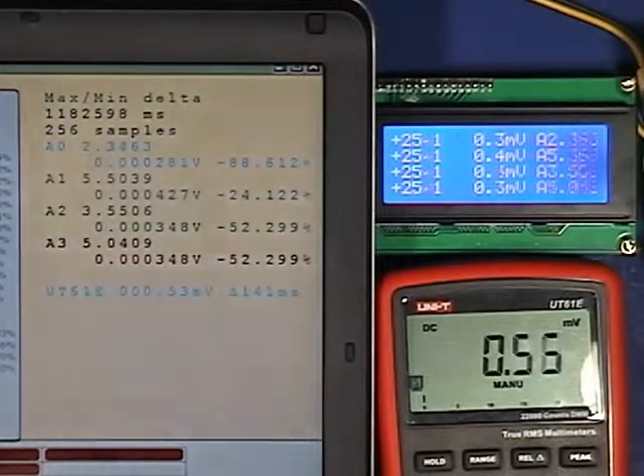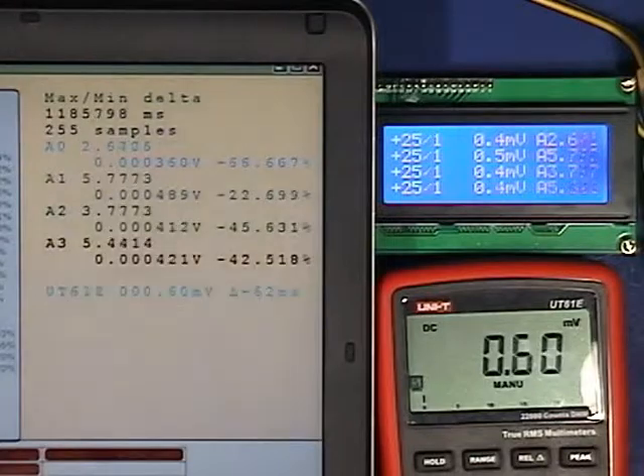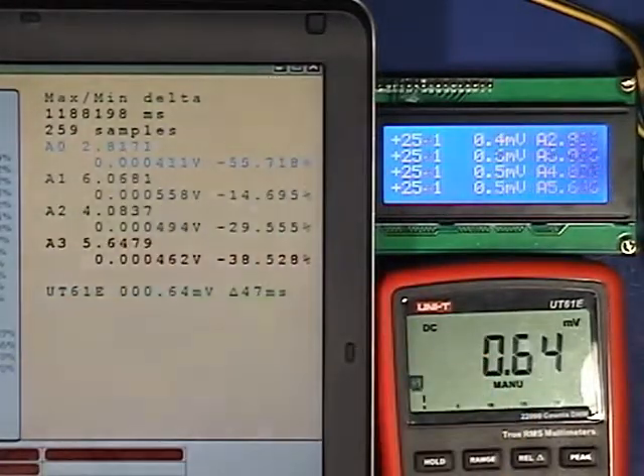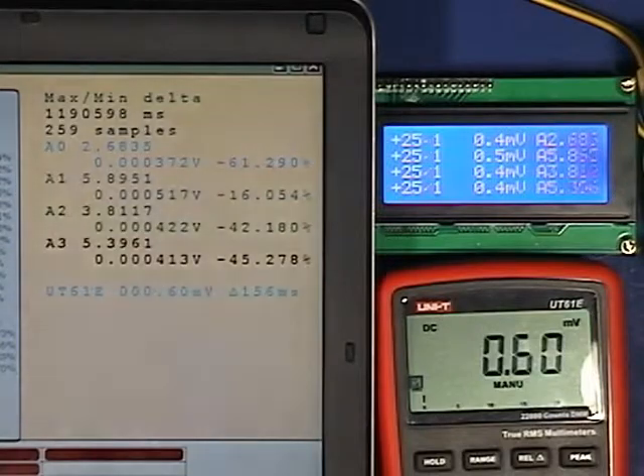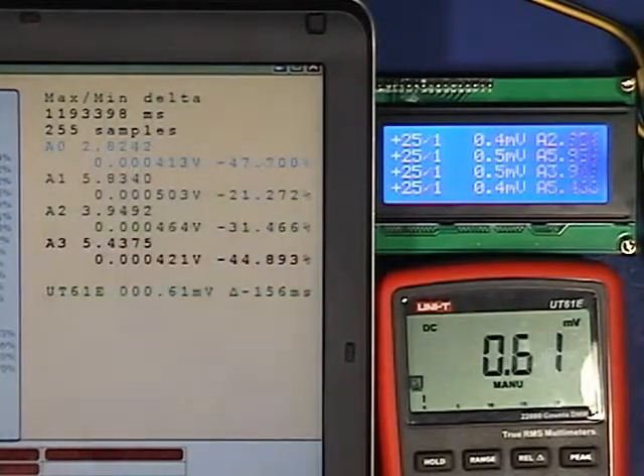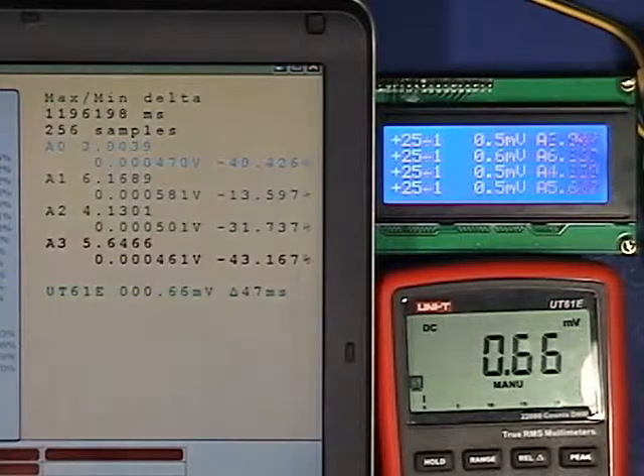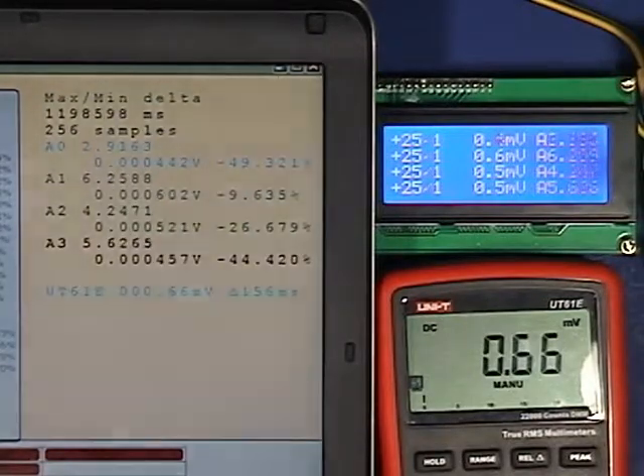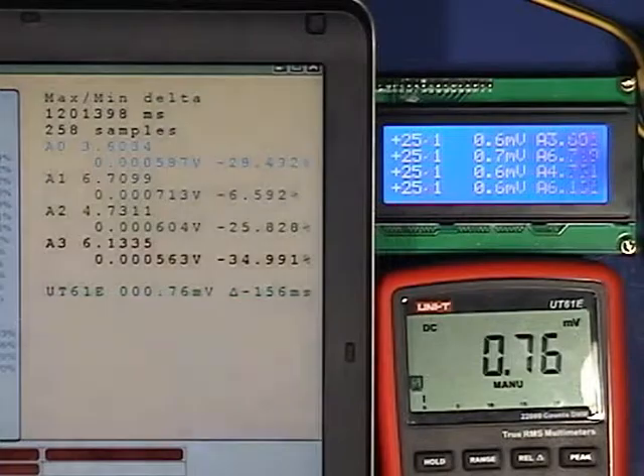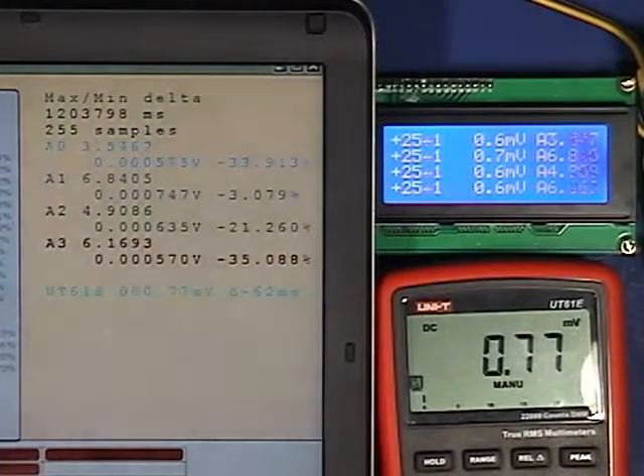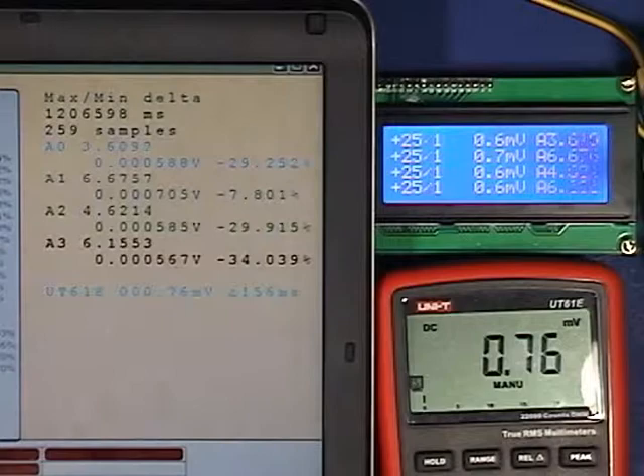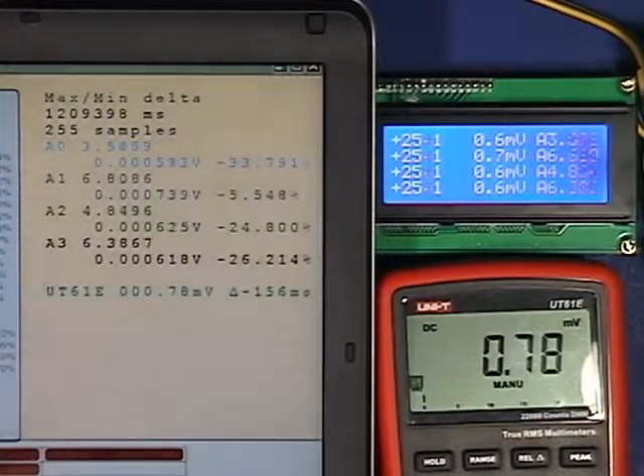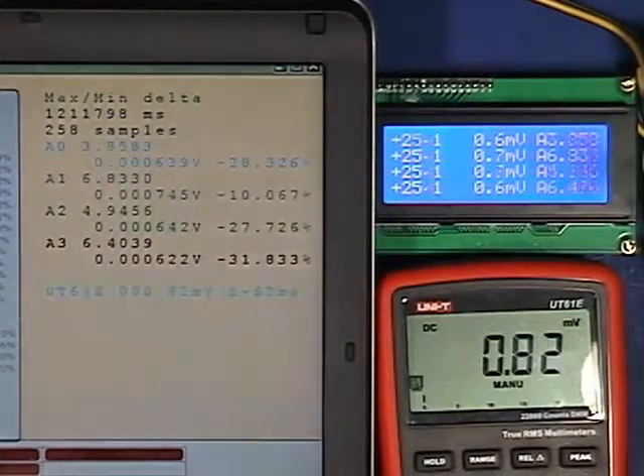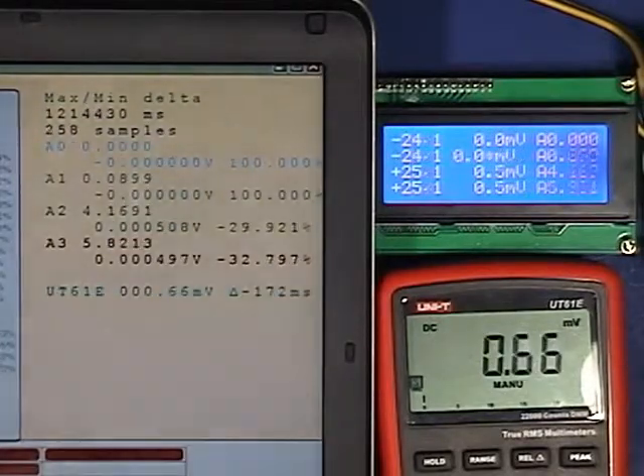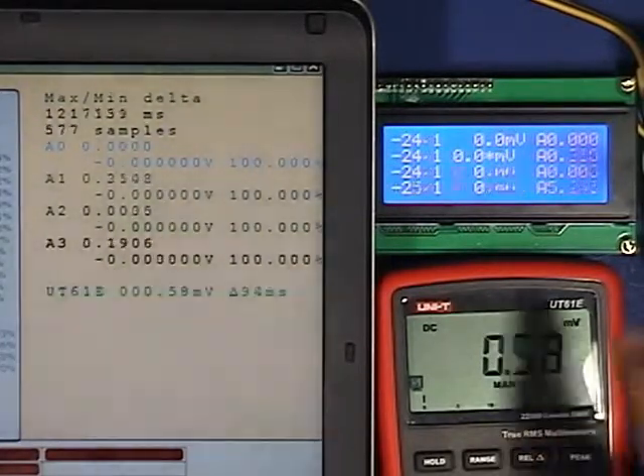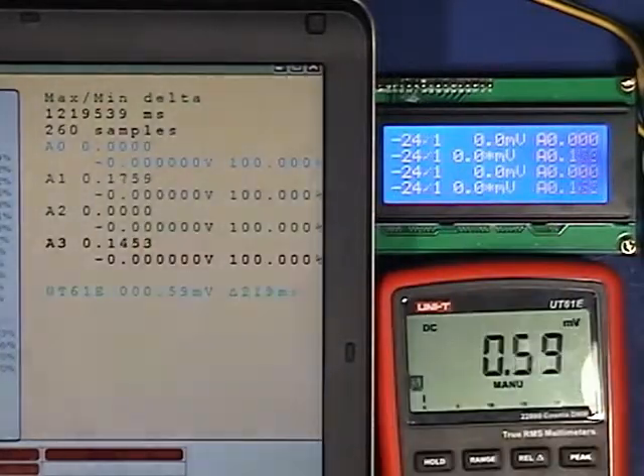At 0.5 millivolt, the error rate is huge, of course, but the number is actually meaningful. 0.4, 0.5, 0.4, and the actual is 0.6 millivolt. So the error rate is very respectable at a multiplier of 25 at the 200 millivolt range. Let's switch the polarity now. So I'm doing the minus 200 millivolt range.